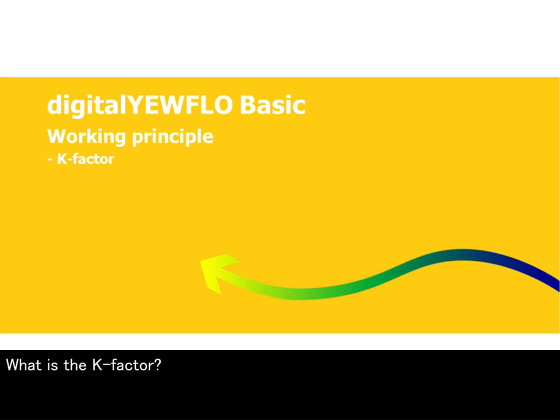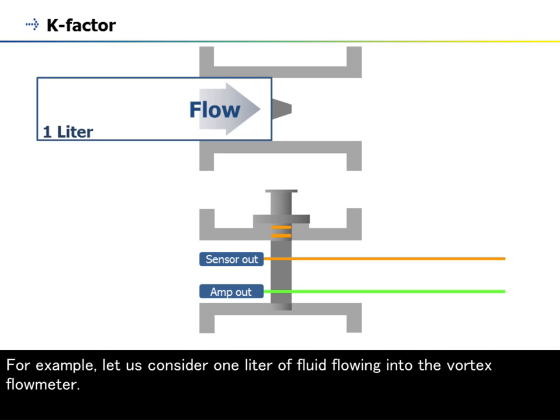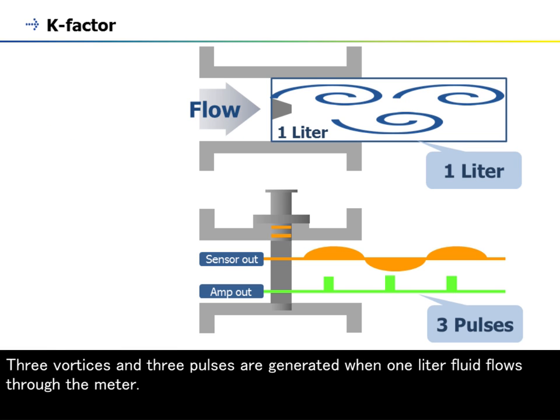What is the K-factor? The K-factor of the vortex flow meter is the number of pulses generated per unit volume. For example, let us consider one liter of fluid flowing into the vortex flow meter. Three vortices and three pulses are generated when one liter fluid flows through the meter.